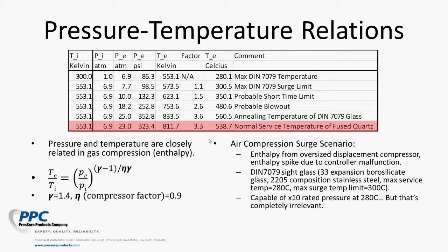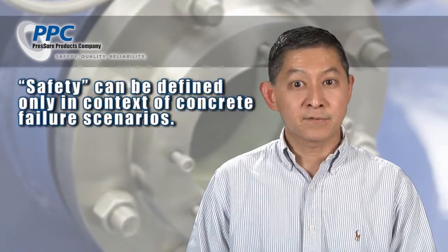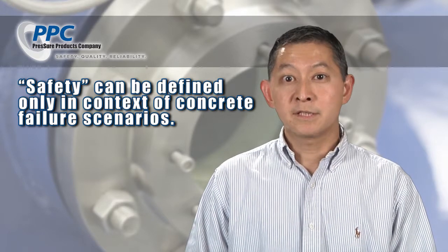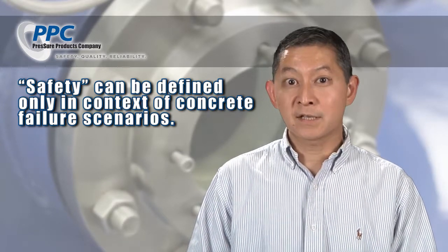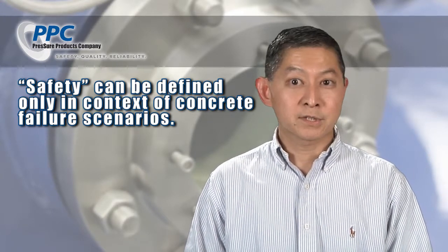The concept of safety cannot be divorced from the process failure scenario you have at hand. In many other scenarios, the DIN 7079 window will provide larger margins of safety. But here, the soft fused quartz glass provides a much larger margin because the scenario is temperature limited. The main take-home lesson I want you to remember is that safety is inherently related to your specific failure scenarios. This scenario I just presented to you is not an exact scenario. We were just compressing air.